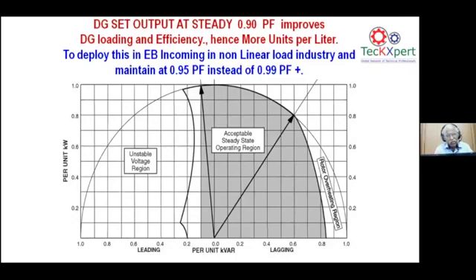You can have the mid region for stable operation. On the unstable region on the leading side, it is a cost loss to the generator, and on the lagging side, less than 0.8 is also a loss to the generator. The alternator definitely gets overheated. So let us try to operate around 0.95 for the genset, as well as from the EB side, by having load compensation for all the machines. You try to maintain around 0.9 power factor.